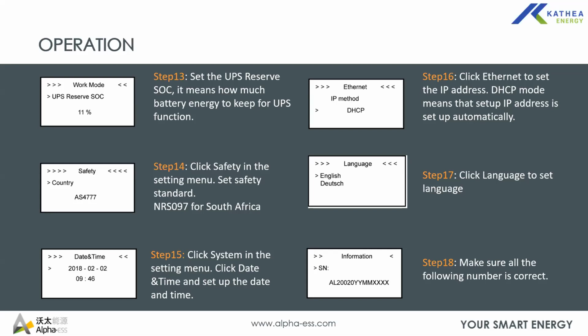The next setting is the safety. Out of functions, underneath functions, there is current safety. Basically on safety, you set the grid code. The inverter is certified for our region, which is South Africa, which is the NRS 097. So you just need to select the country, scroll down for the grid code. It will automatically set all the under voltage, over voltage, under frequency, over frequency settings as standard as per NRS specifications, and all the power factors and all that. So you don't need to set the grid settings manually. And that's the only thing that you need to set on safety.